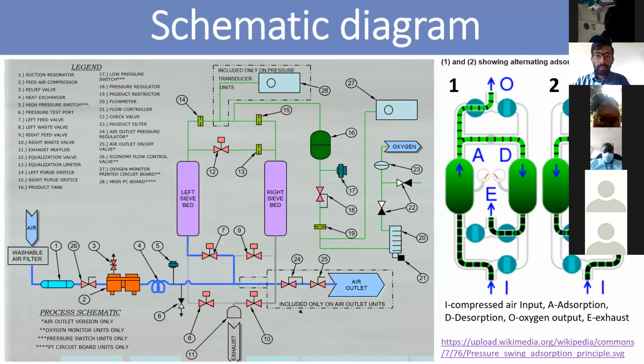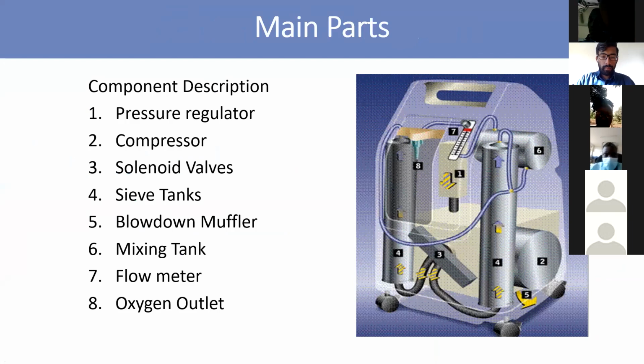This is how it looks. It depends on the model and specification. Some of them have additional sensors or control valves, or maybe an extra flow system. Okay, the main parts of an oxygen concentrator: you're going to see a pressure regulator, compressor, solenoid valve, normally 2 Sieve tanks, blowdown muffler, mixing tank, or sometimes they call it product tank, flowmeter, and oxygen outlet. This is what you're going to see inside your oxygen concentrator.